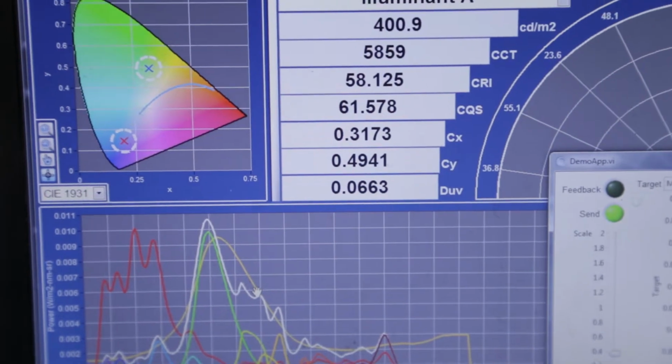The ability to recalibrate the technology in the field, why is that important for customers? Well, think of the downtime you might have in a production environment where you have to take your calibration source offline and then send it back to the factory, which could be 1 to 4 weeks for some companies. All that time is that your product line is down. With this, you take it offline, you put a cap on it, you run the recalibration, you're back up online within hours.